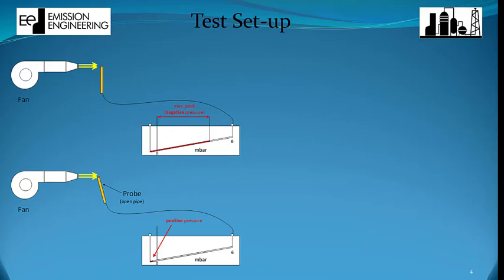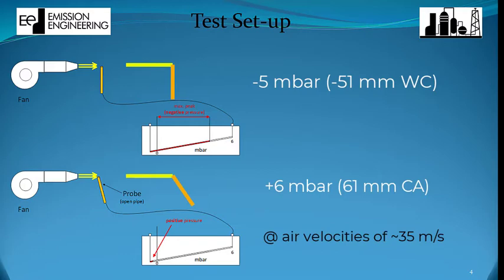As seen in the video, depending on the angle of the tubing, the delta P can be pretty much everything from minus 5 millibar or minus 51 millimeter water column to plus 6 millibar or 61 millimeter water column.